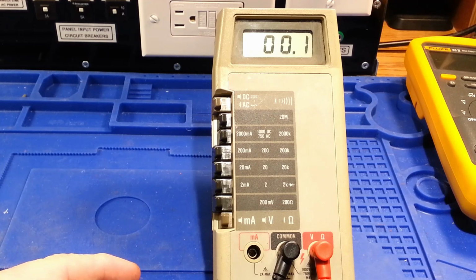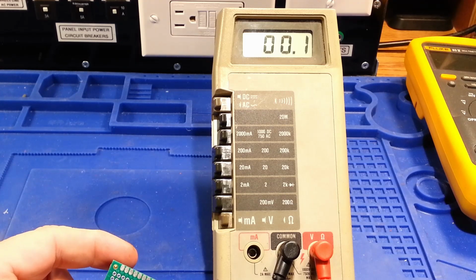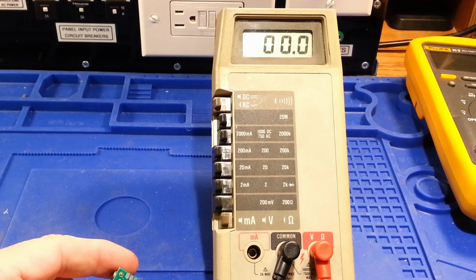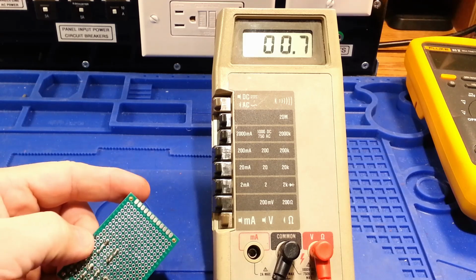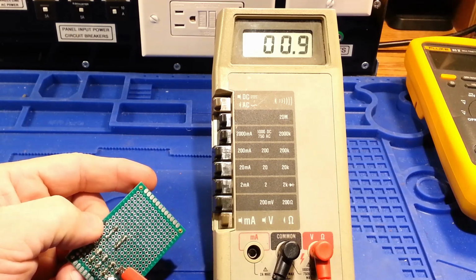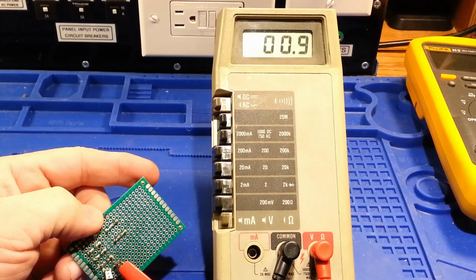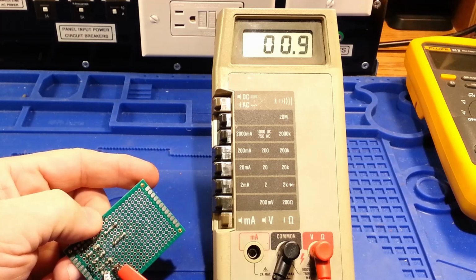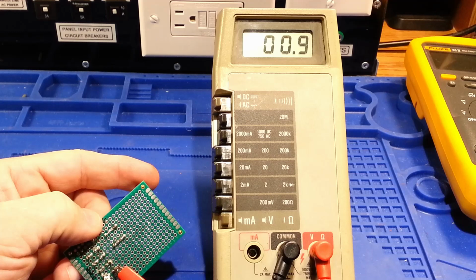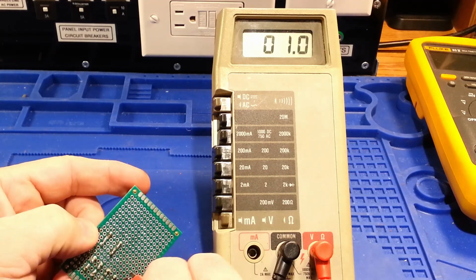So there we are, we're connected. Now granted, we don't have the resolution below that one, but look what we got. We have a 0.1. The 1 gig will measure out in conductance to 1 nanosiemens. So we're going to hook up to one of the 1 gig SMDs, and sure enough, it measures out to just under 1 nanosiemens.